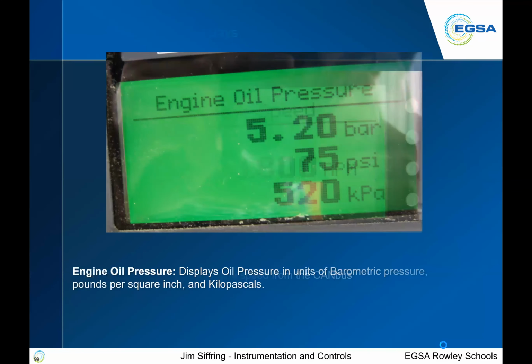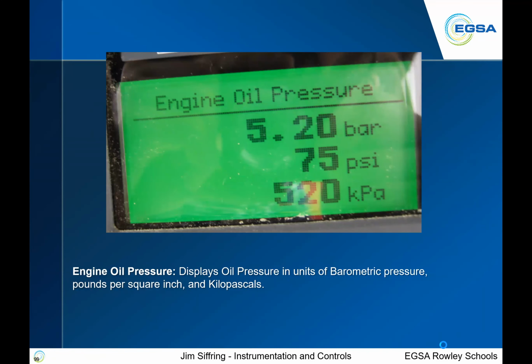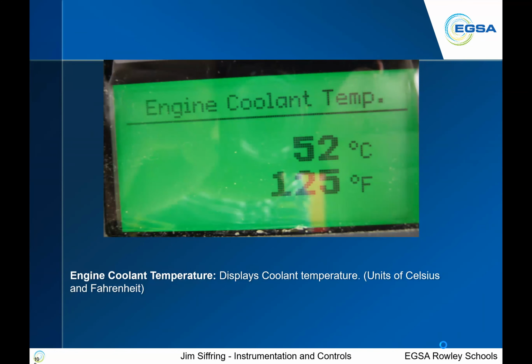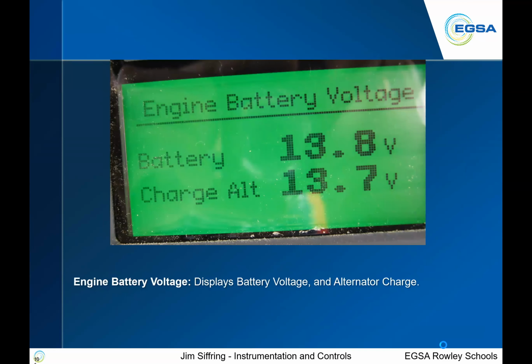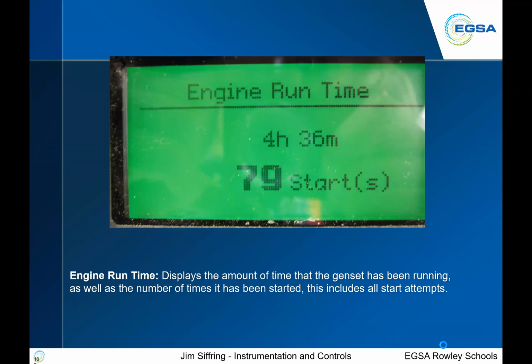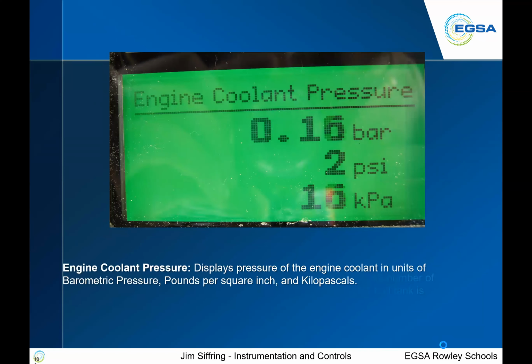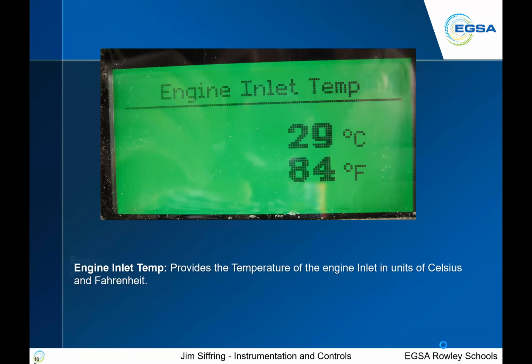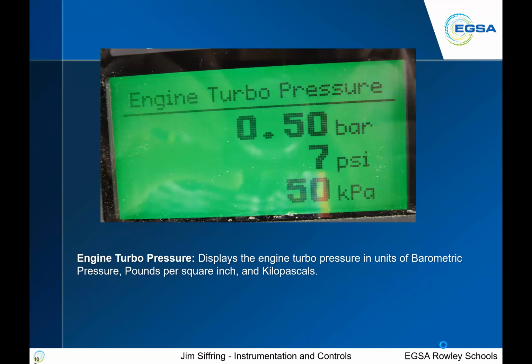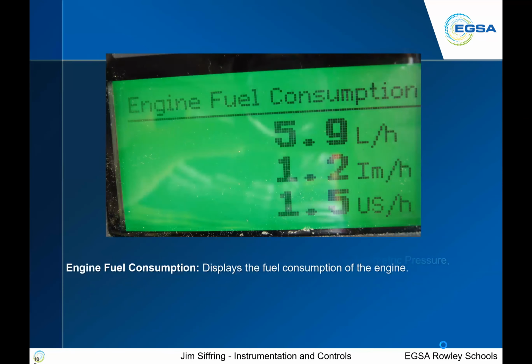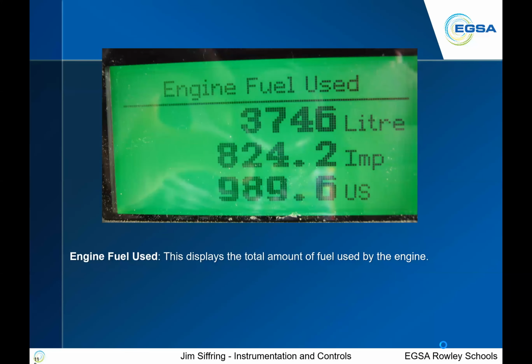So of course you got engine speed and you got oil pressure. Note oil pressure is in bar and PSI and kPa. Coolant temperature in both C and F. Battery voltage, charging voltage. Okay, hours, how many hours of runtime and how many times you started it, fuel level and coolant pressure, inlet air temperature and fuel temperature and turbo pressure in three different types of measurement, and fuel pressure, coolant, fuel consumption. How much fuel has this engine used over its lifetime?